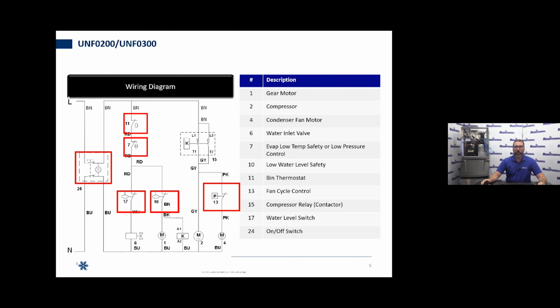So if you have come to a machine, of course, we want to verify that we have incoming voltage to that machine, because if we have a cutout breaker or bad cord or bad outlet, of course, that's going to stop us dead in the water to begin with. So we always want to verify incoming voltage. That's going to be our first step in a machine that's not starting up.